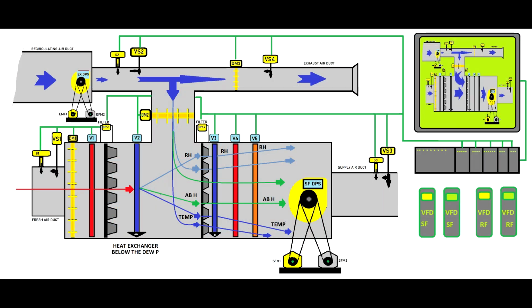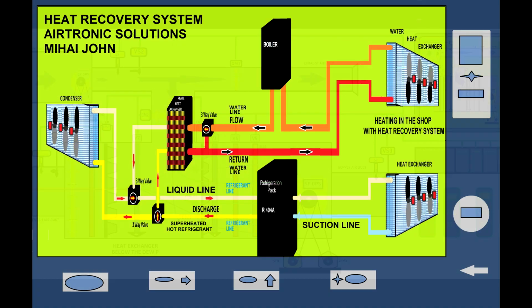Today, I will show you how we can redirect the heat, which is normally eliminated by a condenser when refrigeration equipment removes the energy from a product. So instead of dumping that energy outside into the atmosphere, we can use a plate heat exchanger to redirect that energy into the heat exchangers of the air handling unit to heat the store.